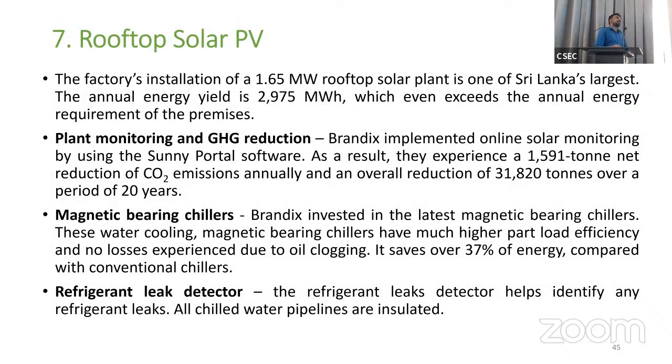And the most important one is the rooftop solar plant. It is one of Sri Lanka's largest rooftop solar plants. It's around 1.65 megawatts. The annual generation is around 2,975 megawatt hours, which exceeded the annual energy requirement of the premises. That means this is a net zero, net positive energy building.